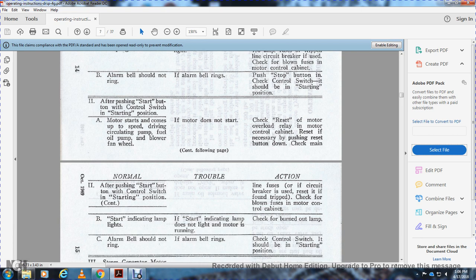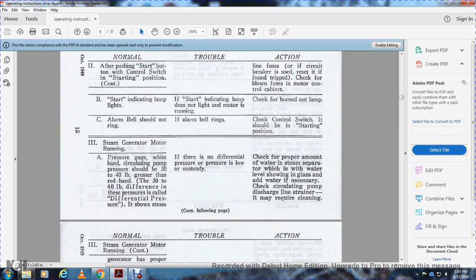Alright, two, after pushing the start button with the control switch in the start position, B, the start indicating lamp lights. Trouble: if the start indicating lamp does not light and the motor is running, check for burned out lamps. C, the alarm bell should not ring. If the alarm bell rings, check that the control switch is in the starting position.